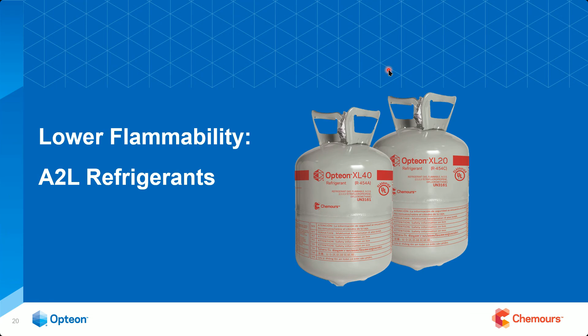When they do this testing, they put the refrigerant in a glass flask or tube and add just the right amount of air. I've actually been to the chambers myself at the Chemours headquarters. They have a magnetic stirring mechanism at the bottom—as we learned in HVAC 101, we need air, a certain concentration of refrigerant, and something to ignite it. They sit outside the lab room watching the chambers, and right when it hits the perfect LFL, they trigger the electrodes and it ignites.